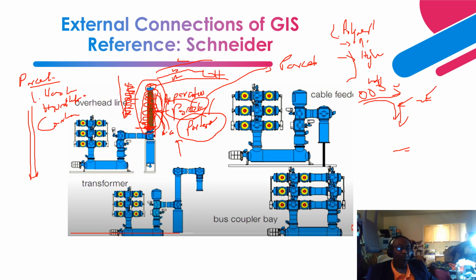Right? So this is an air to SF6, right? Okay, so in here on this side is air. In here is all filled with SF6, all the way. Okay, so now let's talk about the components, right? Okay, so we have an enclosure that has a bus here, right? That is filled with SF6. We have the disconnect switches. We have the earthing switches. We have the CTs. We have the circuit breaker.